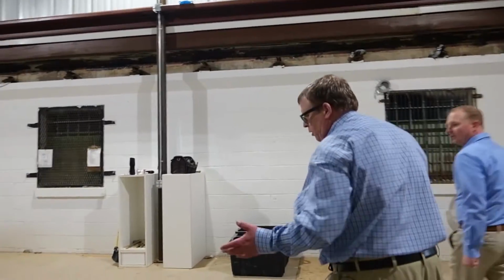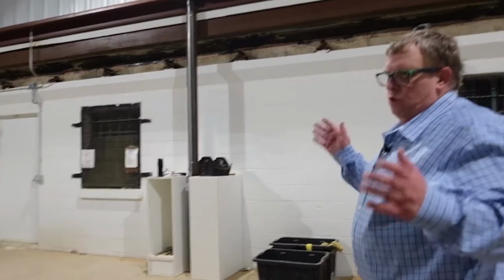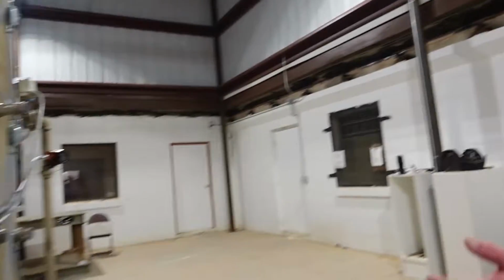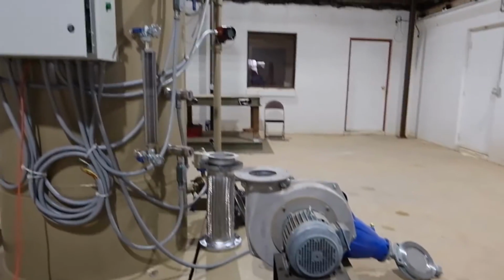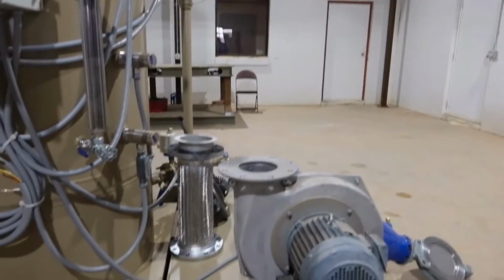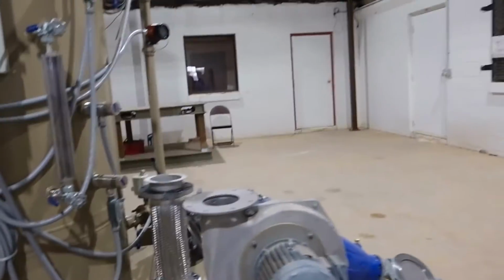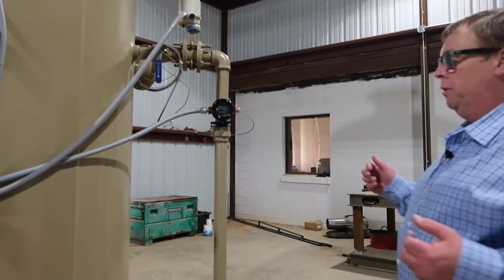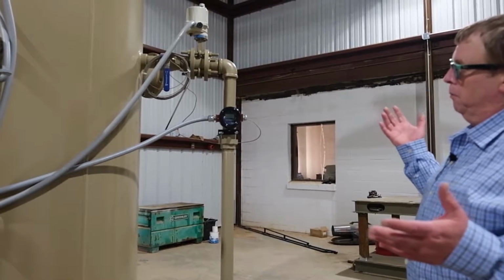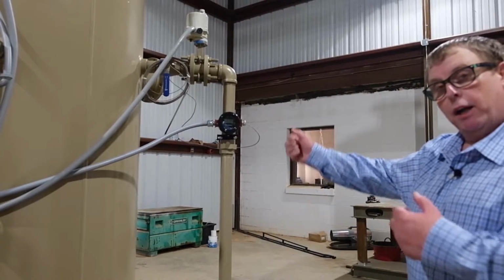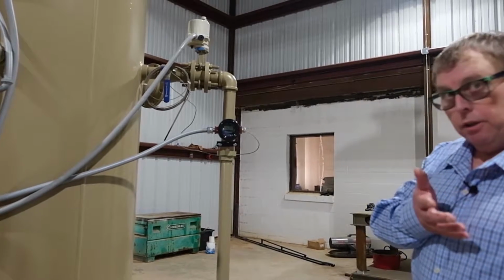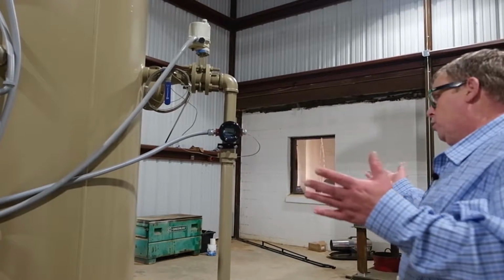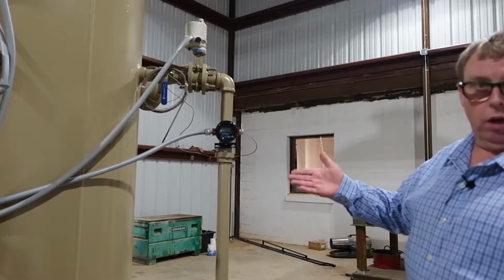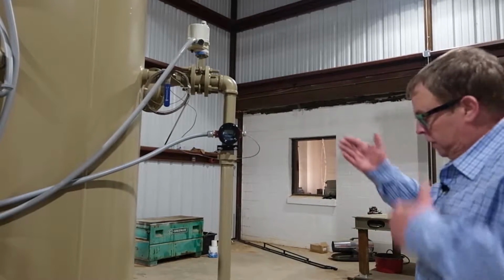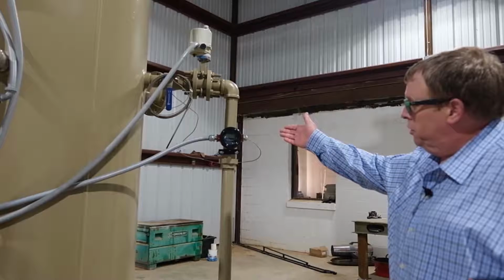What we just spoke about with the blower is treating the first rule that we're trying to accomplish in Quad OA, which is 0 emissions. So we do that with the blower. Going to the second rule that we're trying to achieve is going to be proof of pilot. We use a Moore transmitter to control the communication from the pilot to the client's SCADA system, or whatever automation system they may be using. ROC is one that we have seen some of our clients use. I believe that's what Cimarex uses.